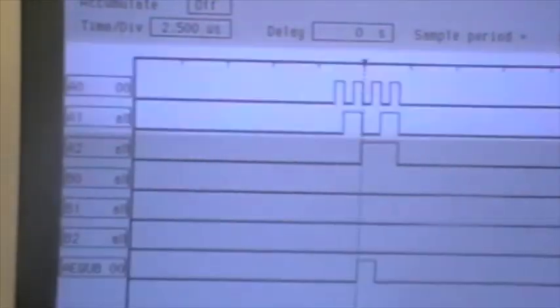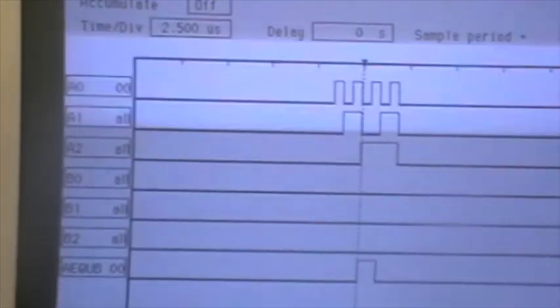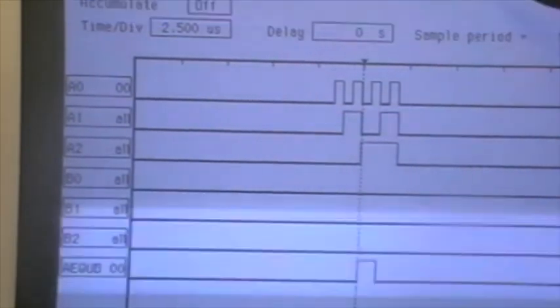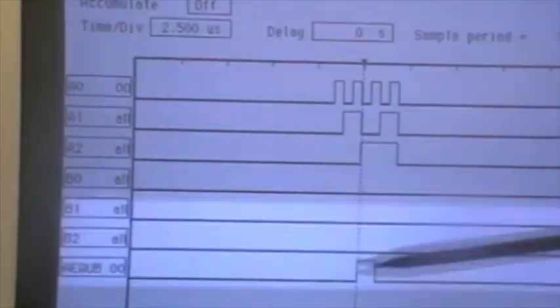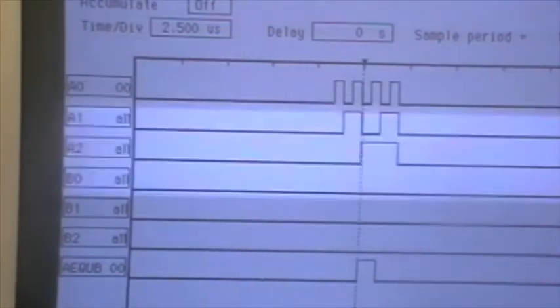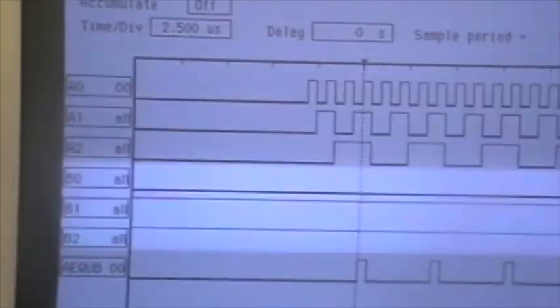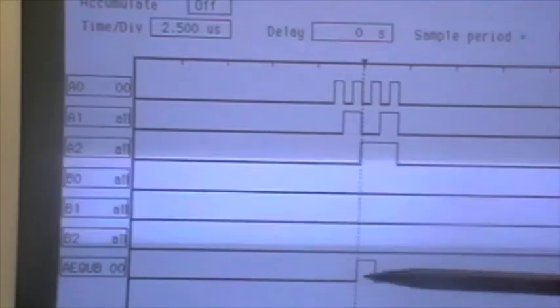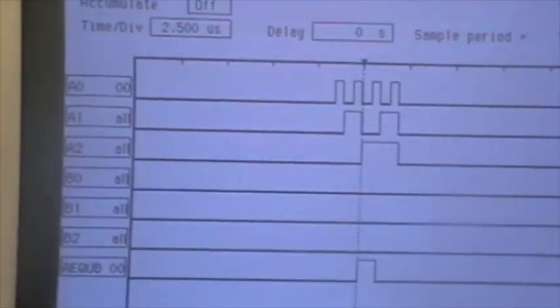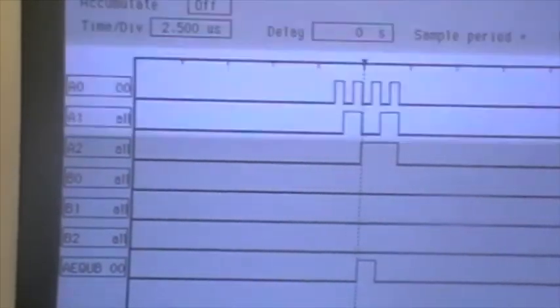And if I go over, so at this point in 10K, the instrument is asking for a trigger, and with this signal, if I stop and run again, I don't have any other signal since my trigger is on the output, right? So I need to switch to the other range. So we have a problem in the comparator output, and I believe that it must be replaced.